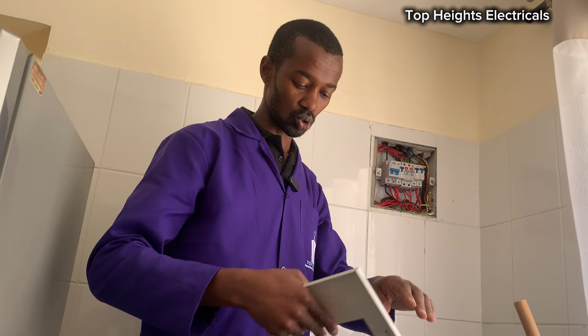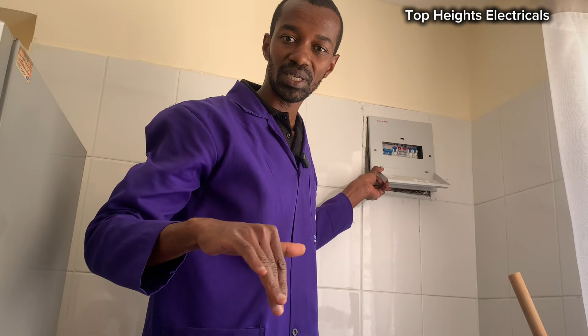So now we have identified that the installation was poorly done upside down. So the only option is to also return the cover in an upside down manner so that the MCBs can have space to safely trip in case of a fault. Electricians in Kenya are surely joking.